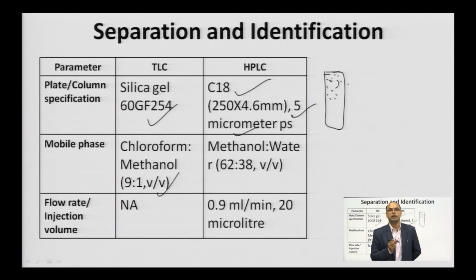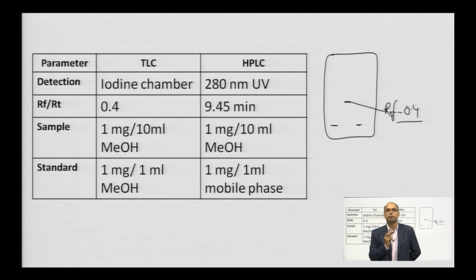A UV detector was used in HPLC analysis. The detector was set at lambda max of 280 nanometer, and a retention time of 9.45 was obtained for podophyllotoxin. It means that after injection of your sample, after 9.45 minutes, the peak for podophyllotoxin was observed on the chromatogram. Here the sample was prepared in the same manner: 1 mg of drug dissolved in 10 ml of methanol, and the standard was prepared by dissolving 1 mg of standard biomarker podophyllotoxin, which can be obtained from Sigma or Merck, in 1 ml of mobile phase. 20 microliter of sample is injected into the HPLC machine. This is the HPLC system which we have used.